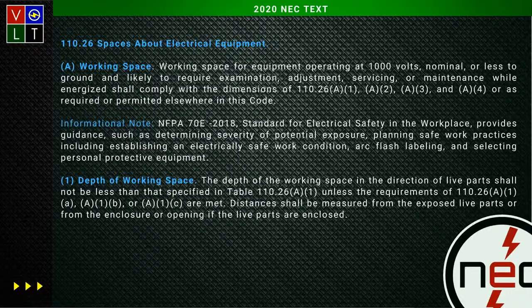And the 70E teacher was like, dude, who's telling you that? I said, what do you mean? He goes, who's telling you it's a code violation? I said, well, that's what I thought. He said, nah, dude, for one, it comes off the energized parts. Then he goes, look at this table. If you're going to use the proper PPE for that installation, here's the calculation right there: this equipment is this and this, and it's going to have this and this. And boom, here's your clearance with a 40 cal suit on: 12 inches.